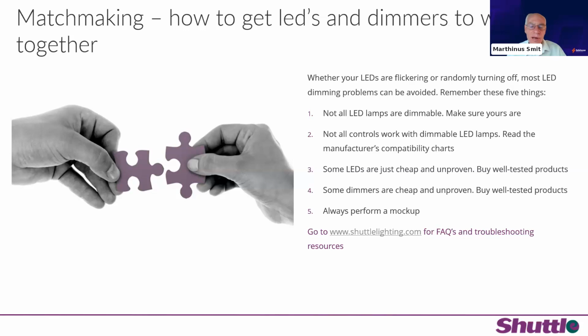Speak to your dimmer supplier. Find out what the maximum loads are that you can place on the dimmer without causing damage to the dimmer, or causing the dimmer to shut down. Some LED lamps are created better than others, so make sure that your LED lamps are fully compliant with the national and international specifications, and work with your reputable suppliers, obviously, and exactly the same for the dimmers. Currently, it is legislation that any dimmer, whether it's manufactured in South Africa or imported, must have a national regulator LOA at present, and so always make sure of that.